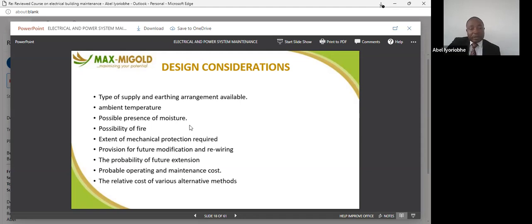Fire outbreak is a factor to be considered. Is your generator or your plant sited close to a petrol station or gas station? We consider that. The extent of mechanical protection required, we consider that. Provision for future modification too. Most people just do the exact recommendation without making provision for future expansion, but there should be room for future expansion.